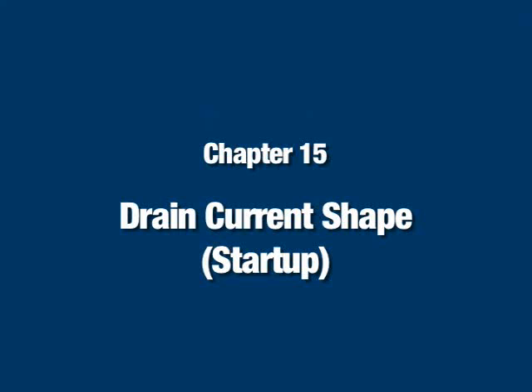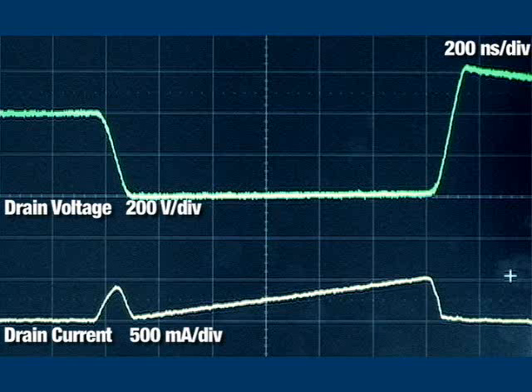Chapter 15. Drain Current Shape Startup. Repeat this procedure while triggering on the drain current waveform and measure the highest current seen during a snap-on event. Examine the shape of the current waveform for signs of transformer saturation.